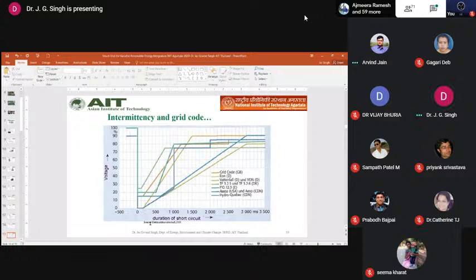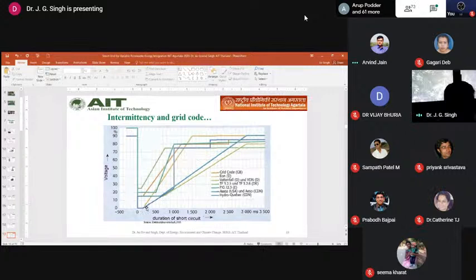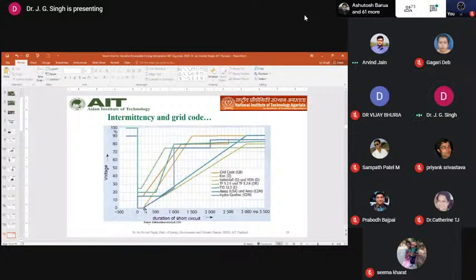Another issue with the intermittency of wind and solar is grid codes. Looking at different countries' grid codes in Europe, some allow zero voltage at the fault location, meaning a three-phase dead short circuit for a very short period before recovery. Some say they can't allow that. Some require recovery from 20% to 80% within almost 1000 milliseconds. So these grid codes differ depending on the strength of the energy supply system in each country. If you have a very strong supply system, you can make very stringent grid codes, which improves power quality and reliability, affecting customer satisfaction.